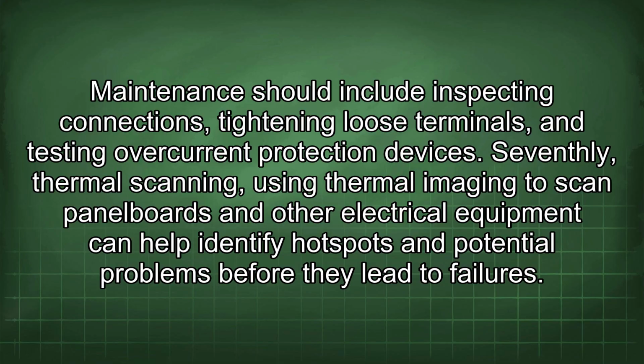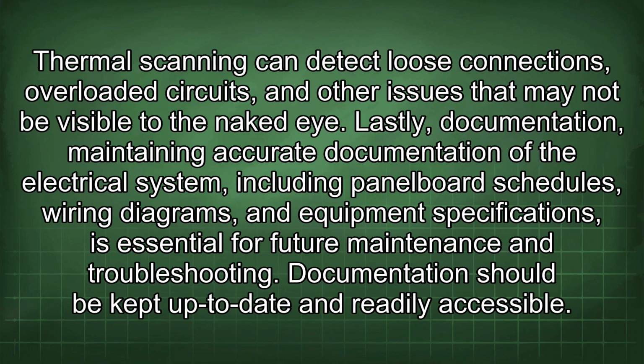Seventhly, thermal scanning. Using thermal imaging to scan panel boards and other electrical equipment can help identify hotspots and potential problems before they lead to failures. Thermal scanning can detect loose connections, overloaded circuits, and other issues that may not be visible to the naked eye. Lastly, documentation. Maintaining accurate documentation of the electrical system, including panel board schedules, wiring diagrams, and equipment specifications, is essential for future maintenance and troubleshooting. Documentation should be kept up to date and readily accessible.